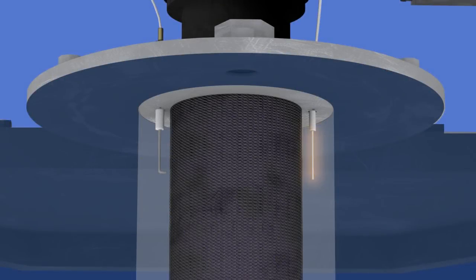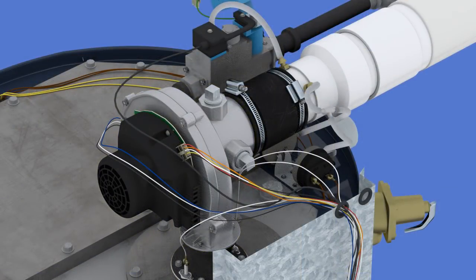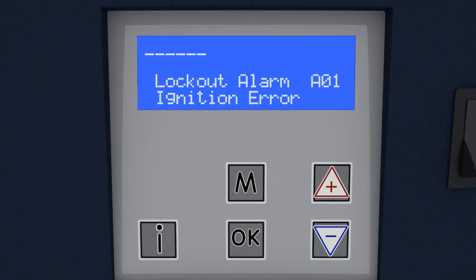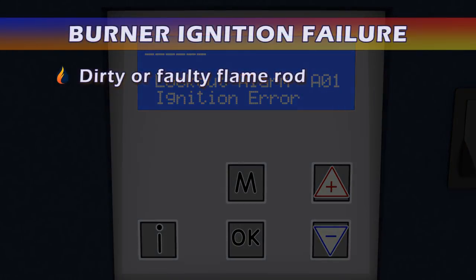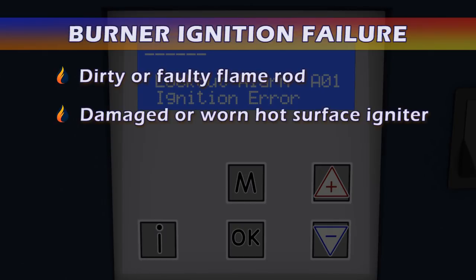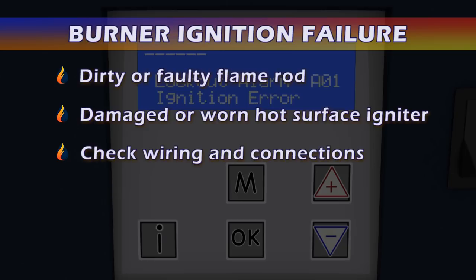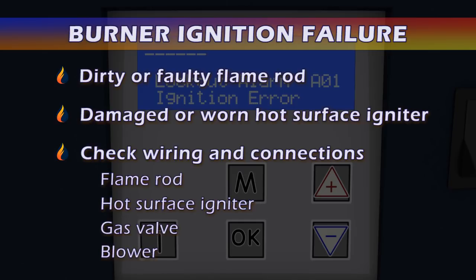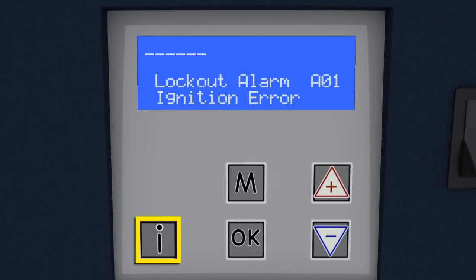If a flame is not established during a trial for ignition, the gas valve closes and the blower goes to a post-purge for 25 seconds. The blower is de-energized and the unit will make 2 more attempts for a total of 3. If the burner fails to ignite after 3 attempts, the control will go into a lockout that requires a manual reset, and an A01 lockout error code will appear on the display. This could be caused by a dirty or faulty flame rod or a damaged or worn hot surface igniter. Check wiring and connections to the flame rod, hot surface igniter, gas valve, and blower. Refer to the manual for more details. Press the I button on the user interface to reset the lockout error.